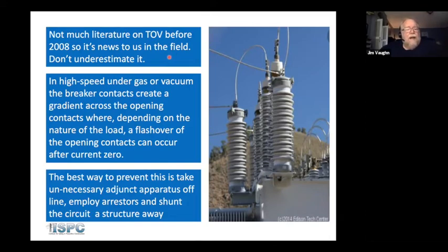And depending on the type of load, which is fault current or reactive load or something like that, depends on the gradient that's created. And if the voltage in the gradient can overload the air gap between the switch, then a momentary restrike occurs. And when that restrike occurs, what happens is that when the switch is opened on, let's say, both sides of a transmission circuit, a voltage was trapped instantaneously on the circuit, and then a second restrike was slammed into that circuit at the same time. So that's a basic estimate of how the TOV occurs.